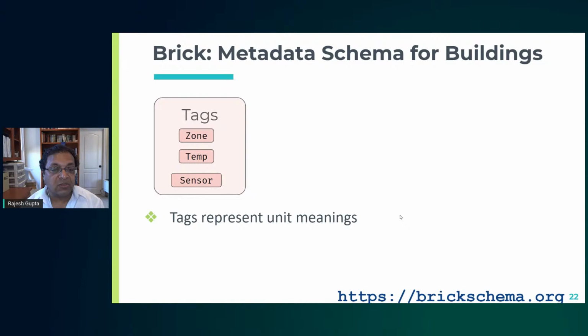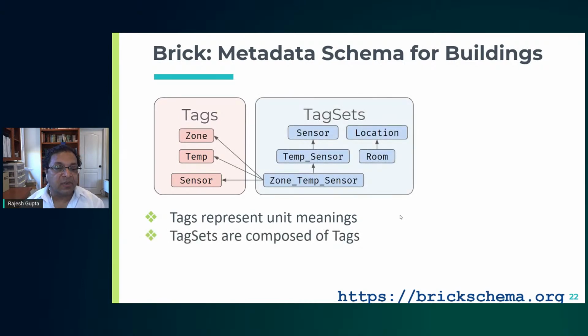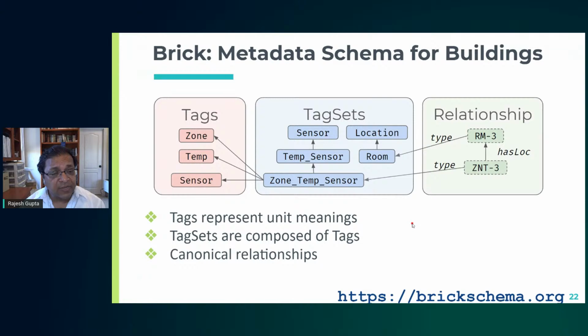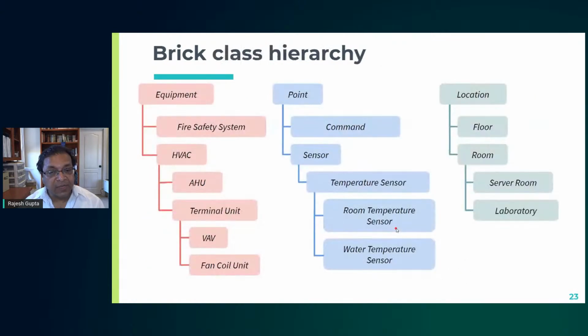So you have tags, which you have seen before. These are tags that refer to zones, temperature, and sensors, let's say. They represent some meaningful object or action. You could also have compound tags or tag sets. For example, a zone temperature sensor, which is a combination of zone, temperature, and sensor. Similarly, you have the location of a room, for example, so you can define the type of a tag. You begin to see that the tags are moving from character strings to having types. And from types, they will get into programming objects. So you can then also define, just like you have types, which are predefined or inherent or native, canonical relationships. And those relationships start to define your model. And that becomes a standard dictionary.